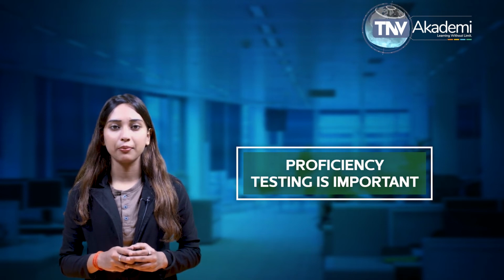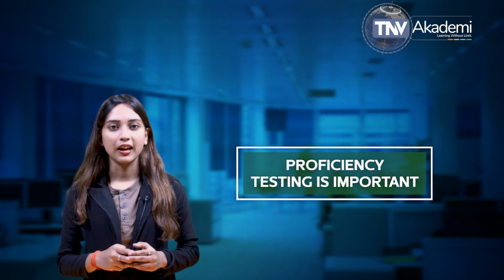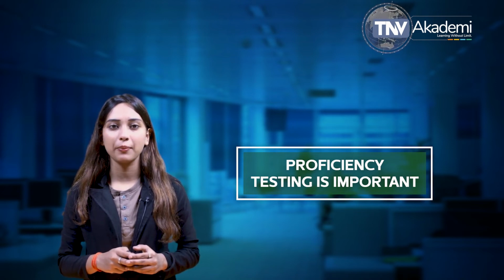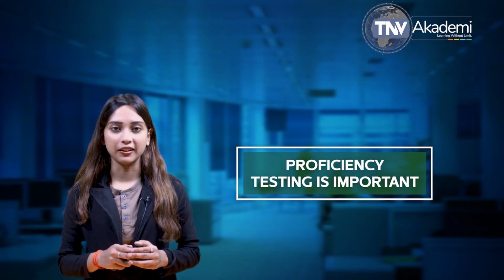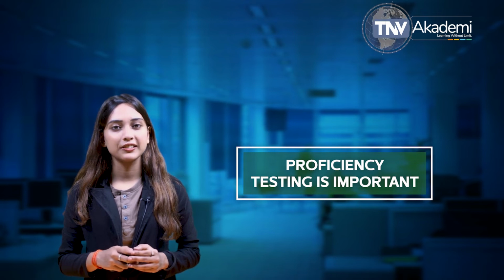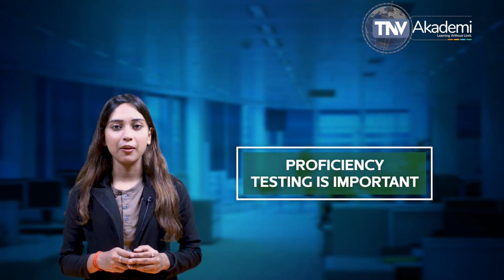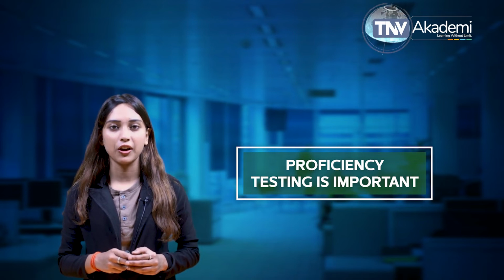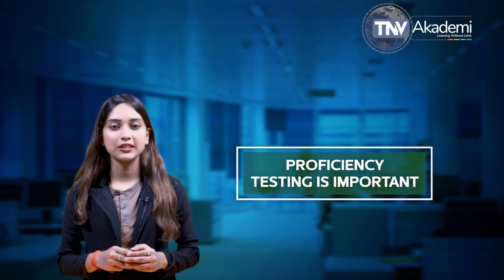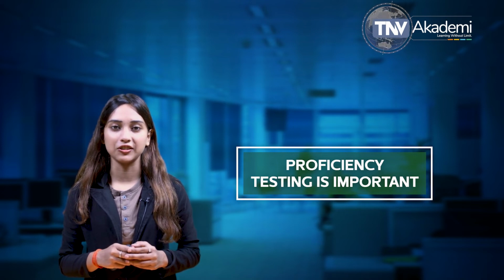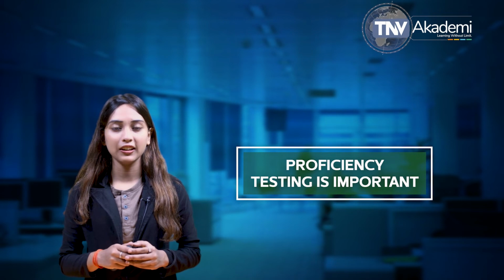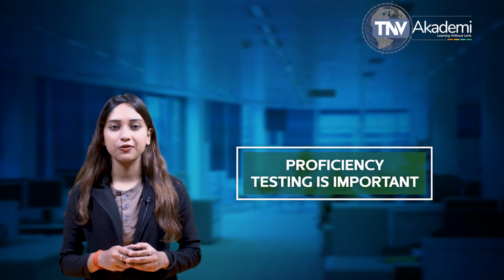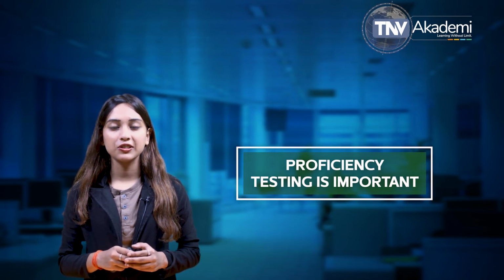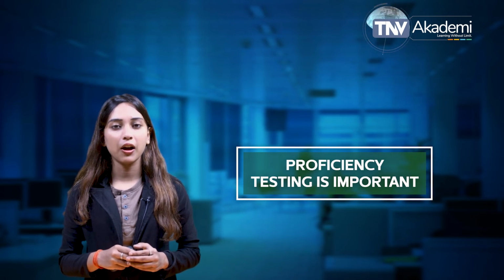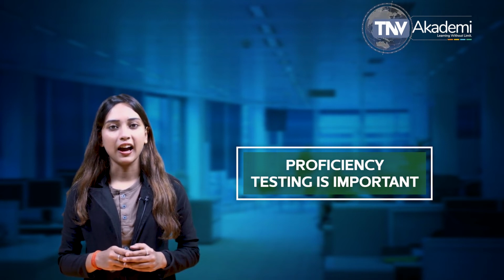17025 Store has received many questions on the topic of proficiency testing, and therefore we wanted to further explain the requirements in order for your lab to become accredited. To become accredited to ISO/IEC 17025, you must meet requirements beyond the ISO/IEC 17025 standard. Understand how to find a proficiency testing provider. Understand your proficiency testing result. Submit your result to your accreditation body. Know what action to take if your organization fails a proficiency test. Not only is ISO/IEC 17043:2010 a requirement of ISO/IEC 17025, it has been endorsed by ILAC and accreditation body policy.